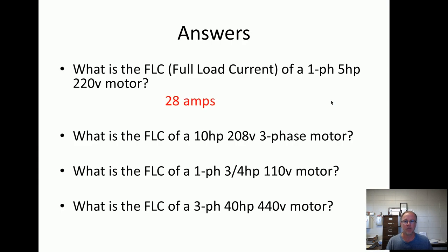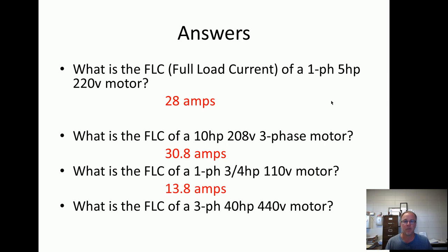Here are the answers. Full load current for a single-phase, five-horsepower, 220-volt motor: use the 230-volt chart — 28 amps. Full load current for a 10-horsepower, 208 three-phase motor: 30.8 amps. Single-phase, three-quarter horsepower, 110-volt motor: use the 115-volt chart — 13.8 amps. Three-phase, 40-horsepower, 440-volt motor: 52 amps.